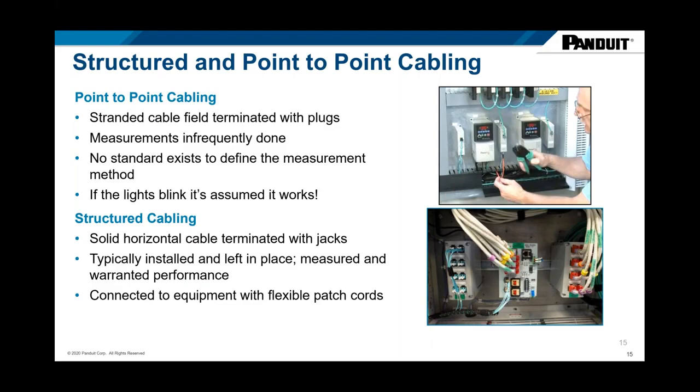Structured cabling to what is referred to as the horizontal connections or the downlinks is also recommended by 1005A. We're down at that EO level in the model. Extending structured cabling to this level provides greater testing capability when commissioning and troubleshooting the network at the edge of the network, or in cabling subsystem 1 in the TIA terms. In certain cases, such as in on-machine field connections, point-to-point cabling is the only option. And the test methods for point-to-point are different than with structured cabling using jacks. So different tests indicate the performance based on point-to-point or structured cabling.